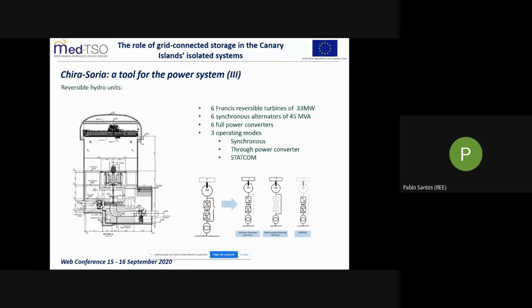The system is comprised of 6 reversible Francis units of 33 megawatts each, coupled with 6 full power converters. That allows us to operate each unit in 3 different modes: connected through the converter, which allows us to fine-tune and control the operation point of each unit; synchronously connected to the network, providing natural inertia to the system; or using the full power converters standalone as STATCOMs.